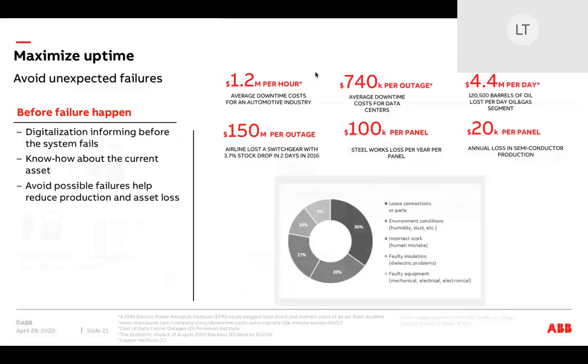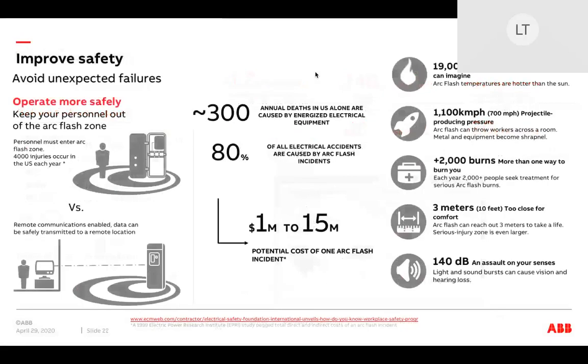Unexpected failures, like loose connections, climatic and atmospheric contamination, etc., will never go away, but condition monitoring and analytics make them predictable. When we look at safety, moving to condition-based predictive maintenance keeps your personnel away from unnecessary proximity to switchgear. Remote HMIs allow for real-time data visibility. As we discussed earlier, arc is the biggest risk to your electrical teams. Don't forget, over 300 deaths annually are recorded in the US alone related to arc or arc blast incidents. If I take a global view, 80% of all electrical accidents are caused by arc flash or arc blast. And then let's not forget the last but most important number to you. Between 1 to 15 million is your potential cost.